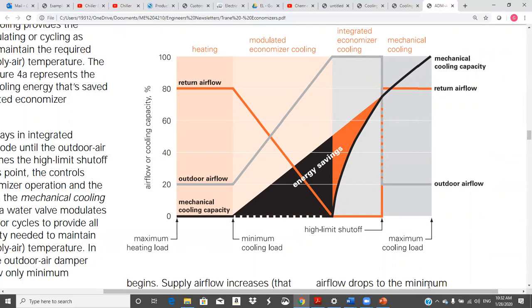Let's say this is 100 Fahrenheit or 95, whatever the design temperature is outside. So this is the outside airflow, and this is the return airflow. Of course, the sum of those would be the supply air to the space. And we see when it's really, really cold outside, we don't want any more of that. It's just too cold. And we're on heating, so you just have to take whatever the code requires for ventilation purposes. Now it starts getting warmer, but we still have constant ventilation air. So we have constant return air because this is a constant volume system. We're blowing the same airflow into the space all the time, okay?